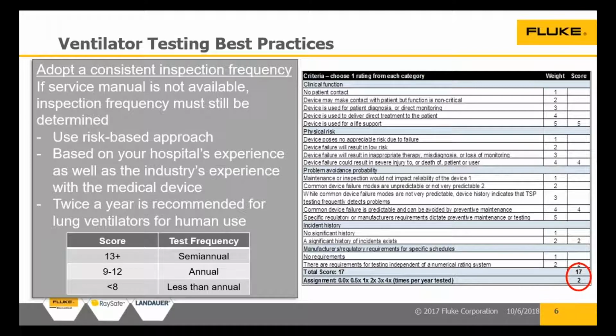But you can't do that without a database that takes your test results in and lets you identify the critical measurements so you can do a long-term trend assessment on them and set some trend limits. When you do that, you get the ability to predict what's going to fail, and then you order your parts, so your affordability and budget management become better, your efficiency of testing becomes better, everything is better. More uptime for the device, which is also a hallmark of a best practice quality assurance program.